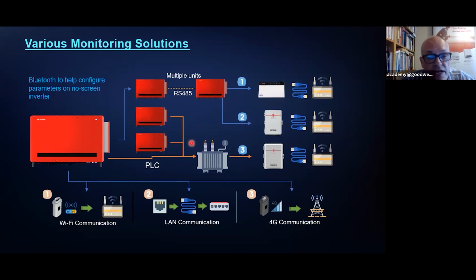Number 3 is our PLC version. If you purchase the PLC version, all the data can be transmitted over the power lines of the interconnected inverters, then finally connected to the transformer at a ground station. At that ground station you need a compatible device to read the PLC data, called the SCB2000. This is also a data monitoring device that transmits data about all the inverters in the system up onto the portal. That's our larger utility-scale monitoring and export control capability.